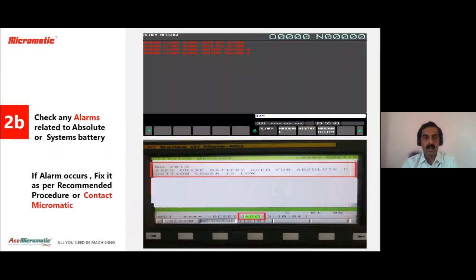Next, if there are alarms, we have to check them on the screen which is shown in the picture. These are absolute or system battery related alarms. If that alarm occurs, fix it as per the recommended procedure. If you don't know anything about this battery replacement or any troubleshooting, then please contact our local nearest Micromatic office so that you will get help and the problem will get resolved.